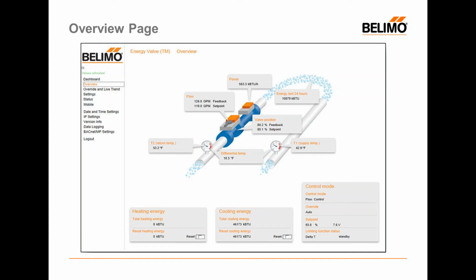If you simply override the analog output, you'll see set point of 100% or 10 volts DC, and the valve won't know that it's being overridden. It will just see a 10 volt signal input.